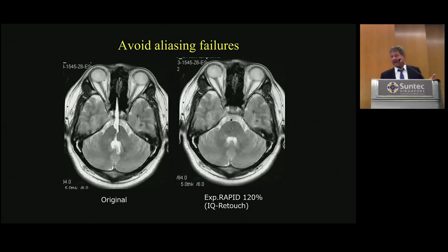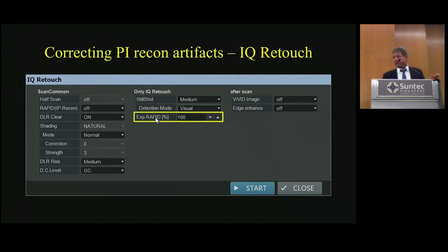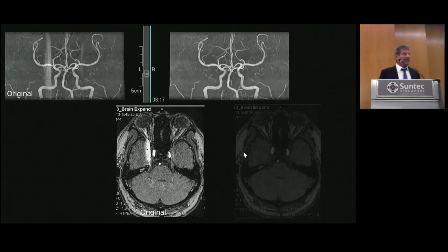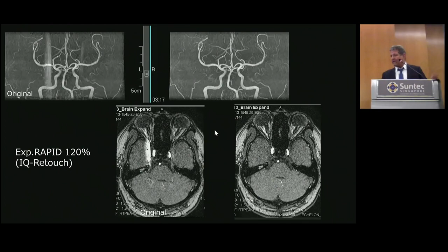I don't have any of my scanners that has the ability to do this retrospectively, and it's just simply a tool you can go ahead and dial up the appropriate change in the field of view and end up with something that would look like this due to this artifact and turn it into something that looks like that without that artifact. Again, just the types of things you'd like to have that you would expect from a state-of-the-art, high-field scanner from a serious MR manufacturer that knew what we needed at the point of attack, the ability to go ahead and save exams, prevent artifacts, and actually salvage artifacts that would have needed a repeat exam.